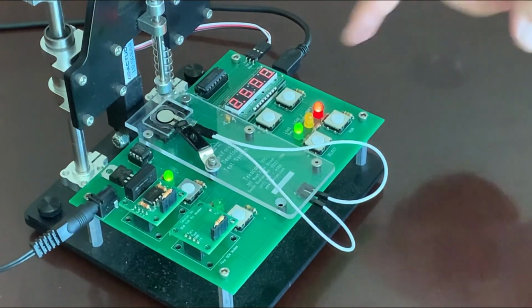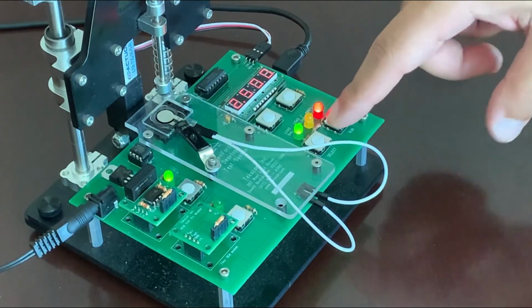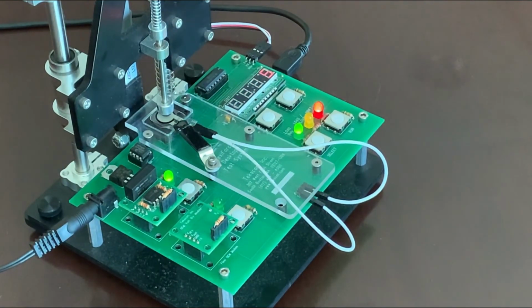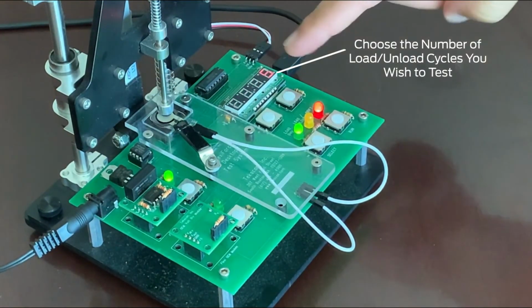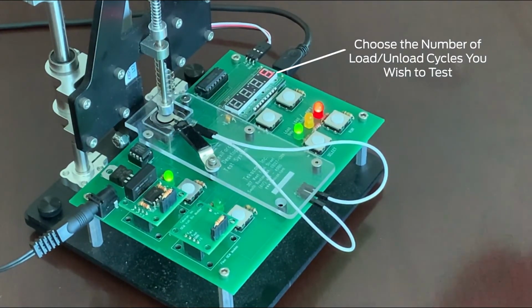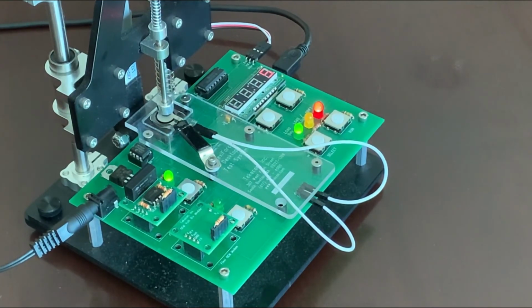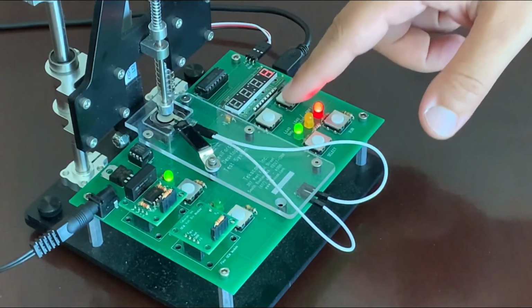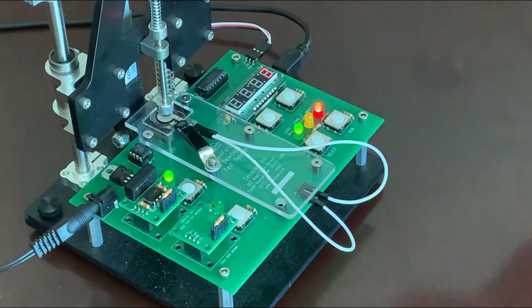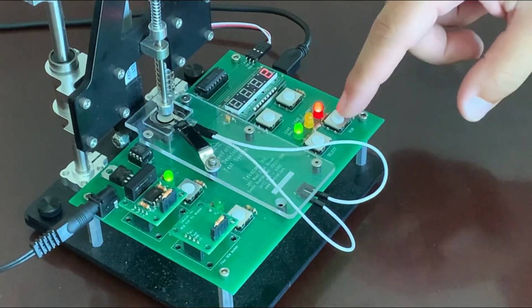So now that we've got the test profile selected, we'll go ahead and run. There's an intermediate step here. You can see the indicator has now changed, displaying a number 5. This is the indicator for how many load-unload hysteresis profiles you'd like to run for this repeatability test. For the sake of the demonstration, we'll just narrow that down to 2. And then we'll go ahead and start the test.